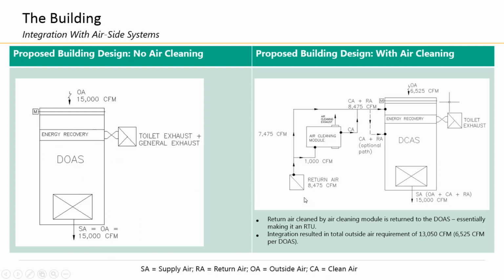How would I apply this? You say basically what you do is you decouple this general exhaust and create a return out of it. We would scrub a portion of that return. Okay, so in this case, you've got 8475 return air. We're going to scrub 1,000 CFM of that, place that 1,000 CFM of clean air back into the return right before the air handler here. You no longer have a 100% outside air system. This is now no longer a DOAS, a dedicated outside air system. This is what we call a DCAS, a dedicated clean air system. Okay, this is a new acronym for you.